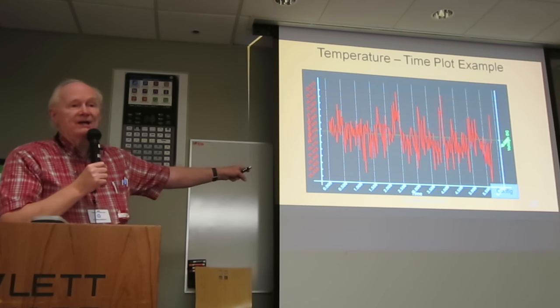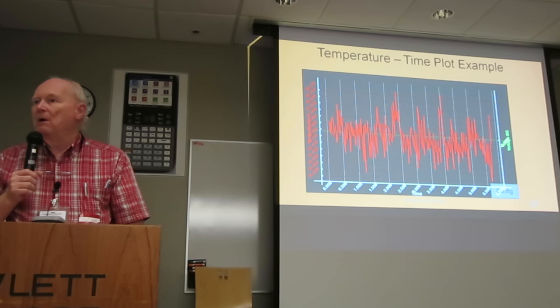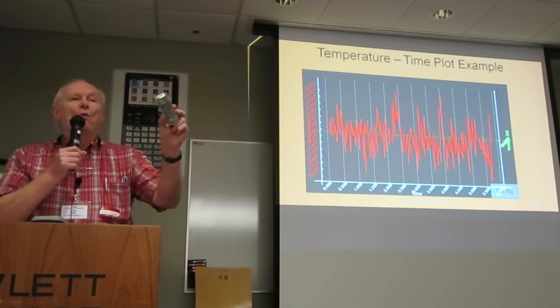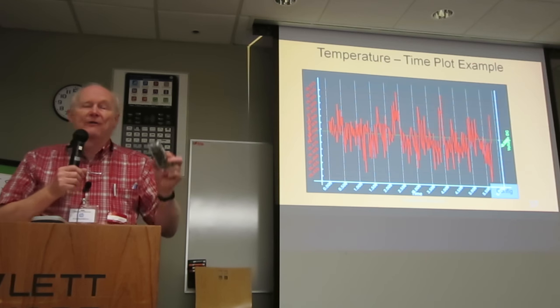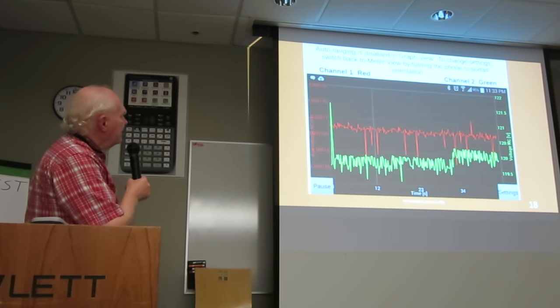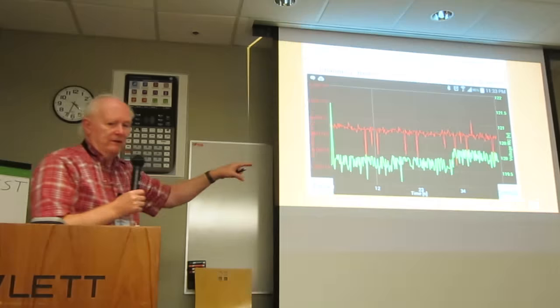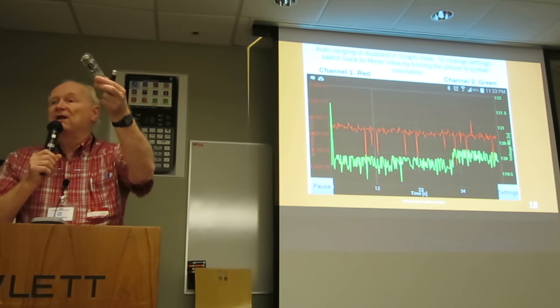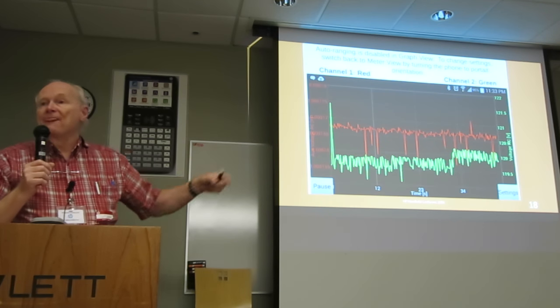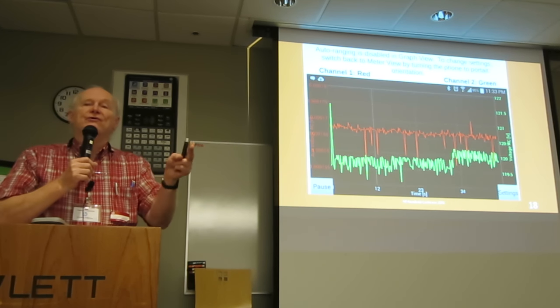In this particular plot, I was measuring the built-in temperature sensor of the device itself — it's more convenient for a quick demonstration. If I wanted to measure an external temperature, I would use a thermocouple and plug it into the two leads. Here's an example of a voltage plot. You'll notice there are three test leads, so you can measure voltage and current simultaneously. One lead represents voltage and another current. You run that into a spreadsheet, do the instantaneous computation for power, and you can get power consumed over time.